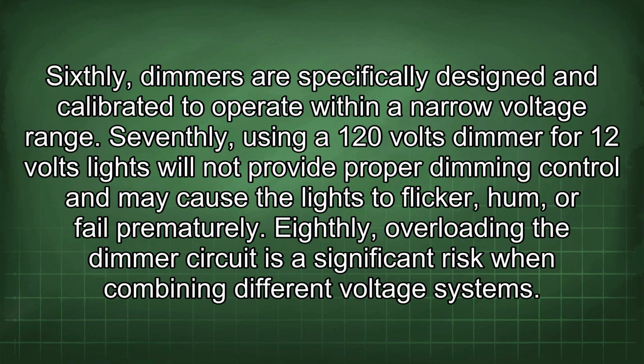Sixthly, dimmers are specifically designed and calibrated to operate within a narrow voltage range. Seventhly, using a 120 volt dimmer for 12 volt lights will not provide proper dimming control and may cause the lights to flicker, hum, or fail prematurely.